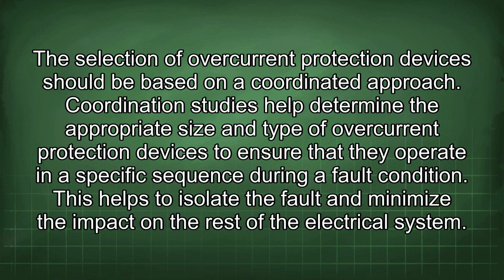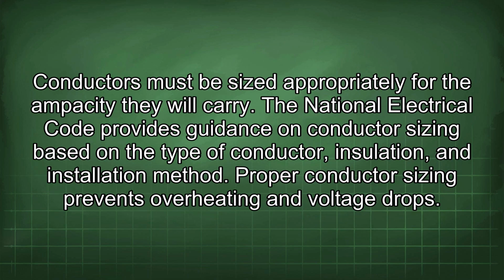The selection of overcurrent protection devices should be based on a coordinated approach. Coordination studies help determine the appropriate size and type of overcurrent protection devices to ensure that they operate in a specific sequence during a fault condition. This helps to isolate the fault and minimize the impact on the rest of the electrical system. Conductors must be sized appropriately for the ampacity they will carry. The National Electrical Code provides guidance on conductor sizing based on the type of conductor, insulation, and installation method. Proper conductor sizing prevents overheating and voltage drops.